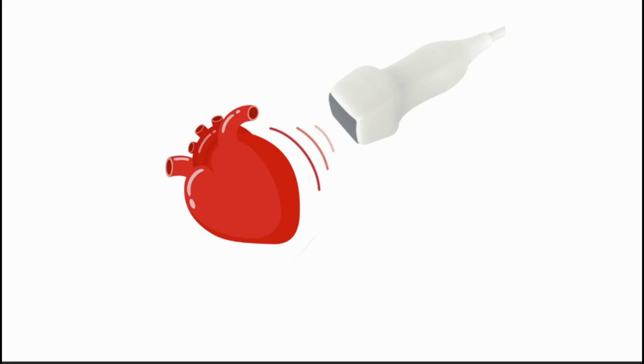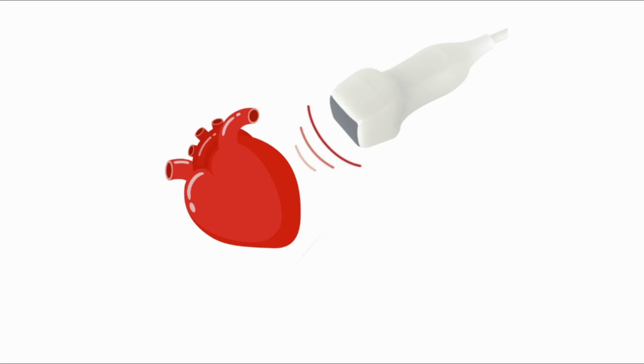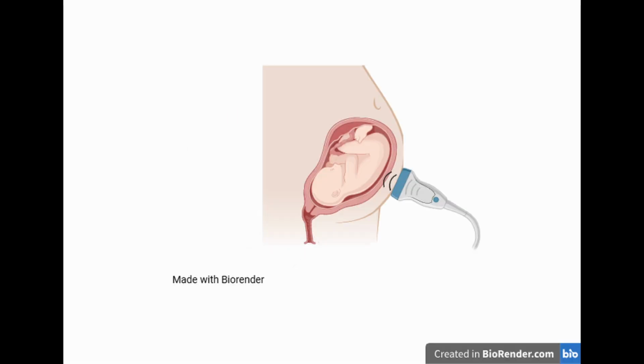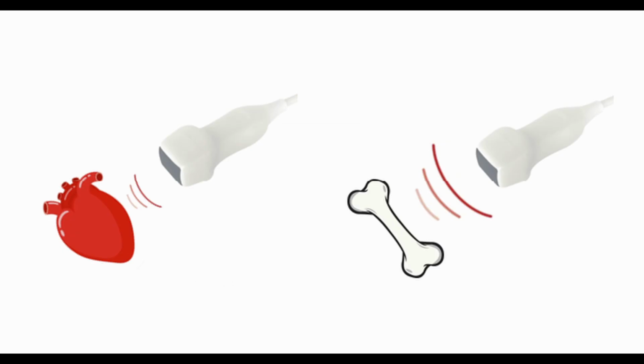The sound wave propagates along its beam path through the tissue and is reflected back towards the transducer by various tissues, like an echo. The time it takes for the sound wave to travel back to the transducer is directly related to the depth of each tissue. This time delay is recorded by the machine and indicates how far the sound has traveled.